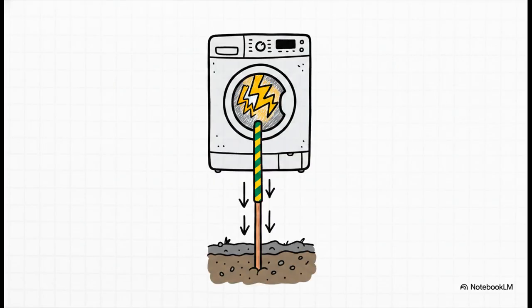But hey, what if things actually do go wrong? Let's say a live phase wire inside your washing machine somehow comes loose and touches the metal casing. If you were to touch that machine, you'd get a horrible shock. And this is exactly where the green and yellow earth wire steps in. It connects that metal casing directly back to the consumer unit's earthing block.